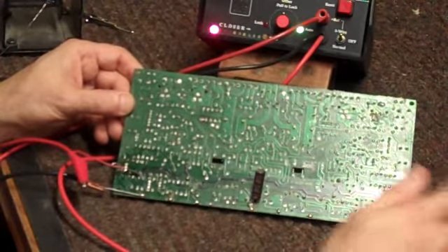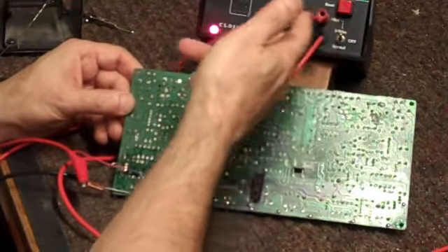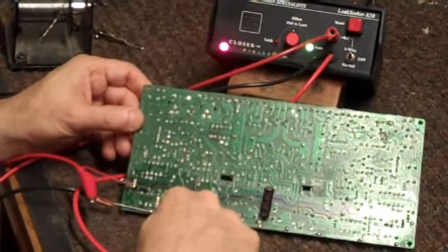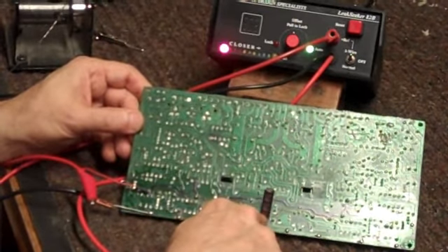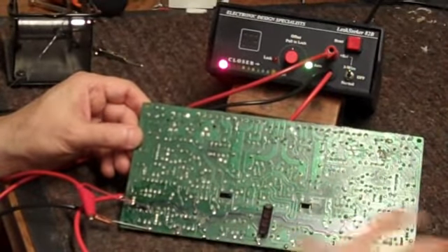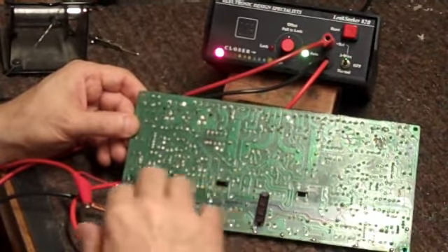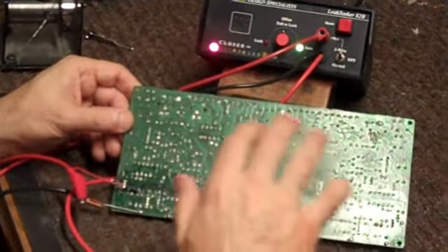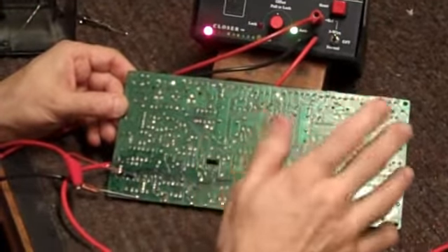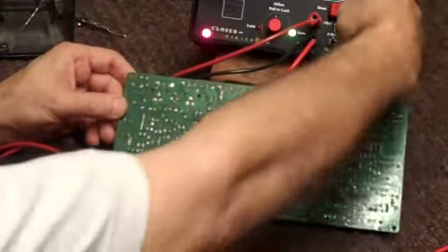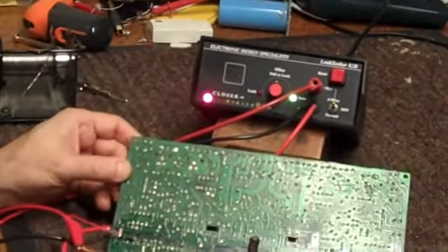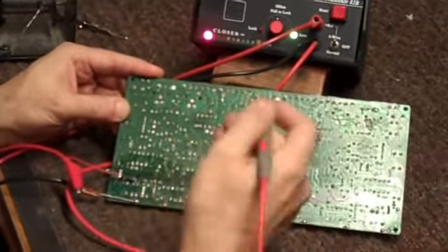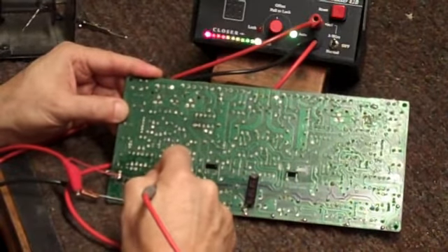Now what's happening is the calibrated current and voltage is coming along here, and this capacitor at this point is charged to a point. Now it's happy, everything is calibrating, all the temperatures are calibrating, so now we can start getting a stable reading. So I'm going to push for a new test as usual, and start probing along. It doesn't matter where I start, but I'll start here.